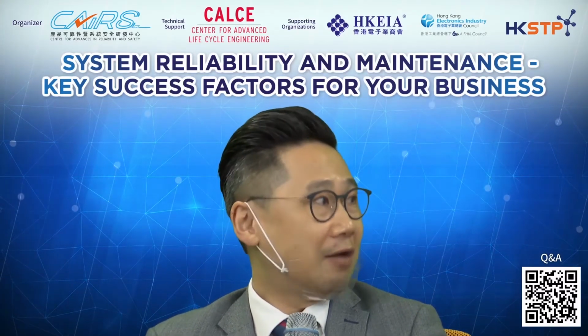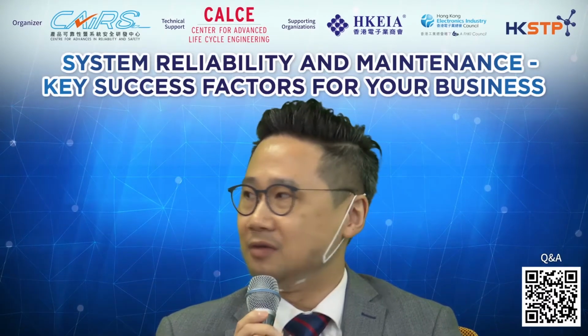As a power company, we usually take a more pragmatic approach. We have our own maintenance schedules, and based on AI, condition-based, or predictive maintenance, the system comes up with another kind of maintenance schedule. But we won't be very aggressive at first. For example, if we schedule maintenance every year and the system tells us we could do it every two years, we won't jump to that immediately. We do it pragmatically and progressively, maybe taking an approach like 1.3 or 1.5 years and seeing how it performs and how the system reacts. If there's buffer to further extend the maintenance schedule, we'll extend it further, to 1.7 years and eventually to 2 years.